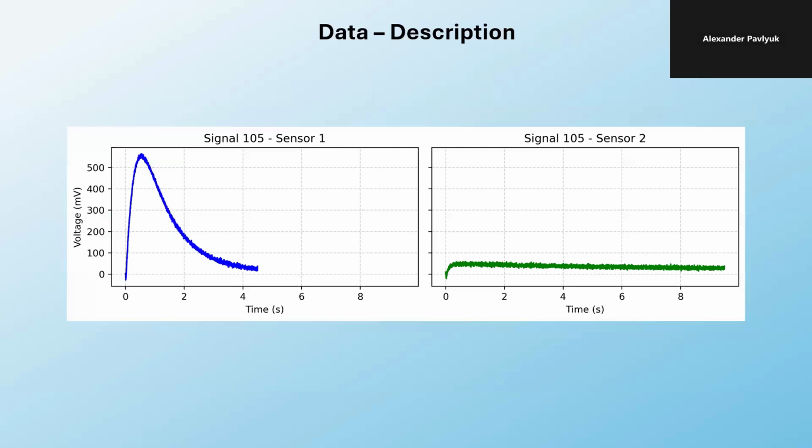You can see the comparison of 2 different sensors for the same concentration. The sensor on the left is new, the sensor on the right is very old, and the amplitudes are very different, and therefore the first sensor produces consistent results, while the second one is very inaccurate.